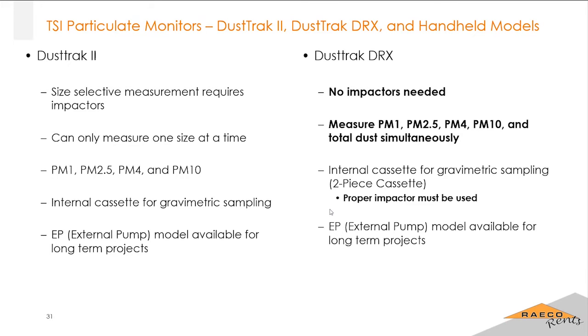Similar to the EVM, the DustTraks do have an internal option for using a cassette. So you can get a sample with that, send that off to a lab. It is important too that you use the correct impactor with that still. So if you're using the DRX and a cassette, make sure you're using the right impactor. If you're using the DustTrak 2, it can only measure one size at a time. So at that point, it's very important to make sure that you're using the correct impactor based on what you're sampling for. PM4, PM2.5, those seem to be of interest to our customers the most from what I've seen.